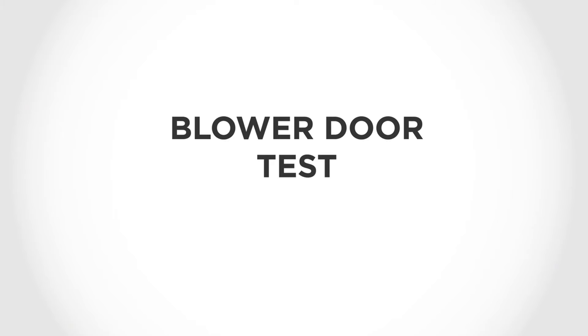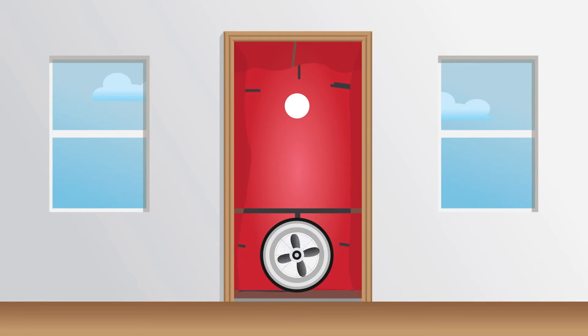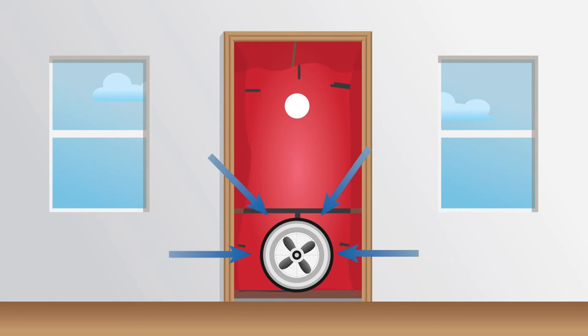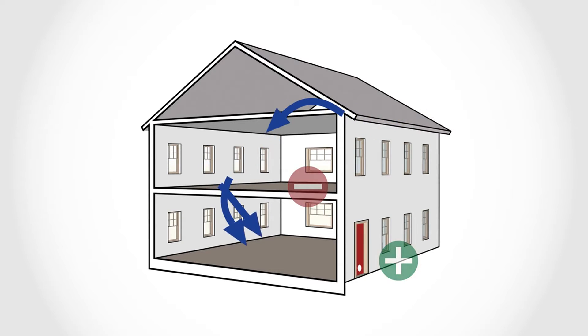A blower door is a high-powered fan that is set in a doorway to create pressure between the indoors and outdoors. This pressure differential pulls air in through all the leaks and cracks in the house.